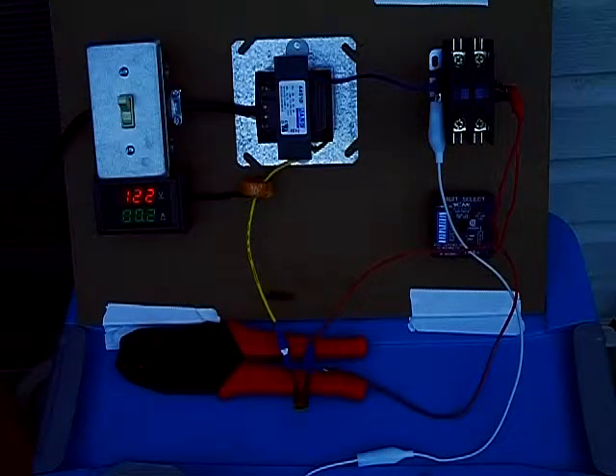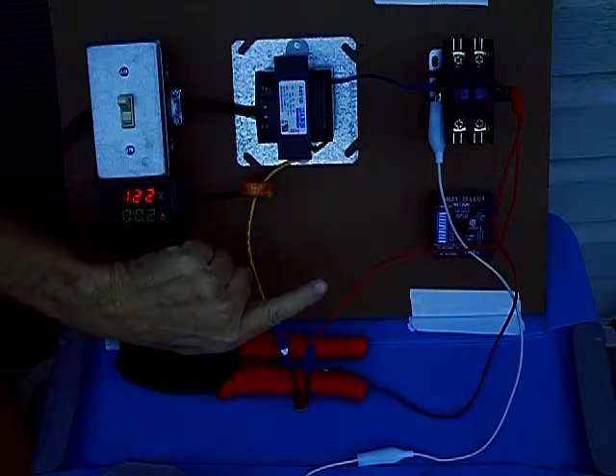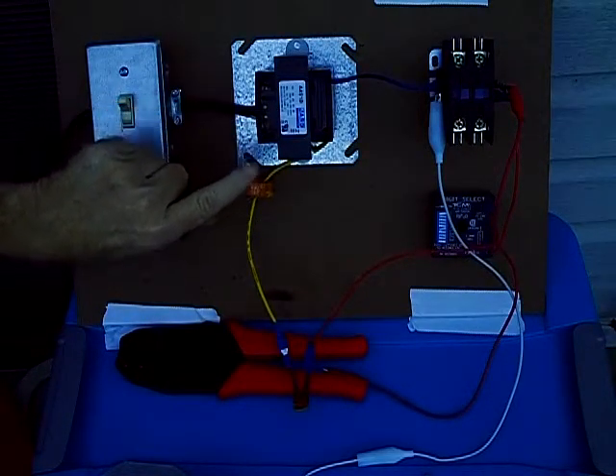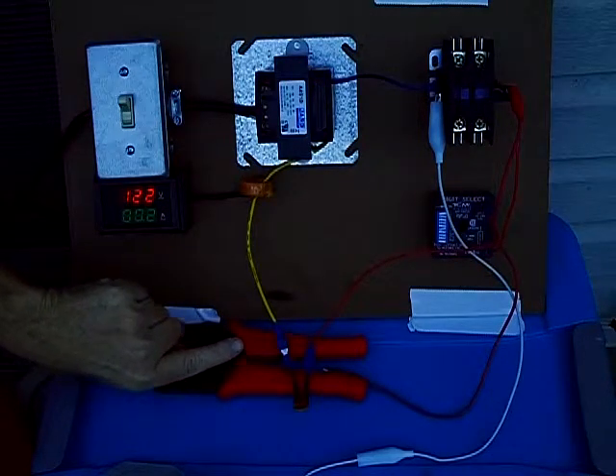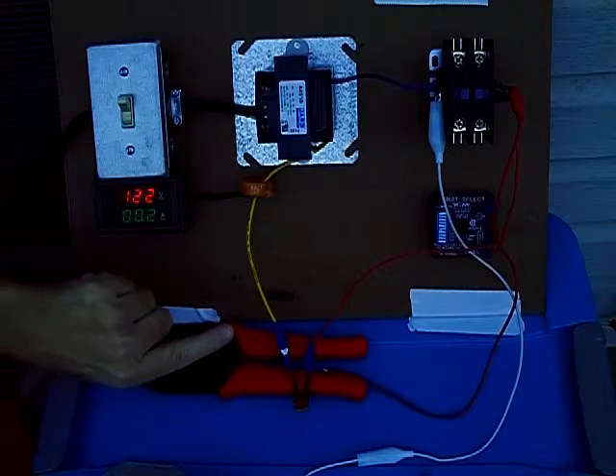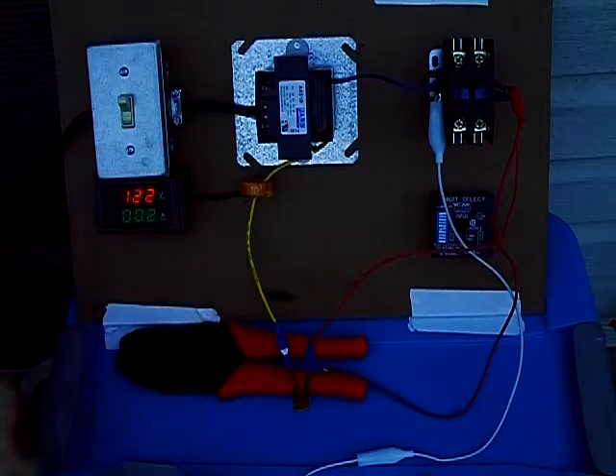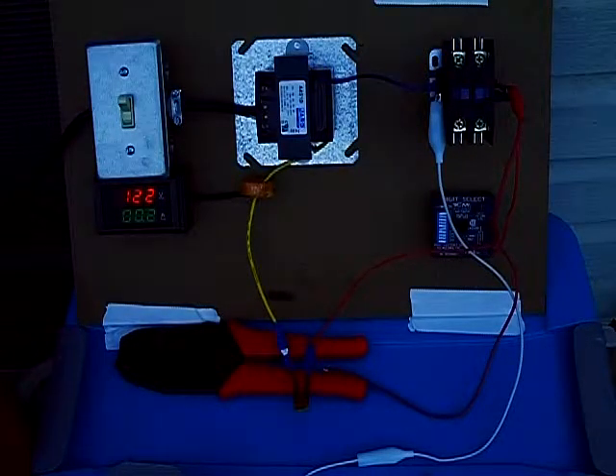So what you want to do is put the resettable fuse in there, to make sure you don't have that problem with the customer being upset or having to go back right away. Wire in an inline time delay coming right out of the transformer. Depending on where your fuse is, you definitely want to go through the fuse circuit first, and then go through your inline time delay. You can wire it in like that, and when it gets that quick short and that short separates or is eliminated, then that timer will allow it to time out to 30 seconds, a minute. You want to set it for at least 30 seconds to a minute to allow that to reset and re-engage, and the customer is not without the cooling or heating.